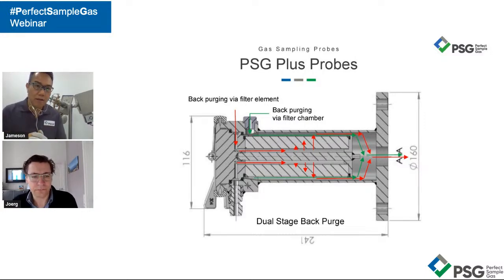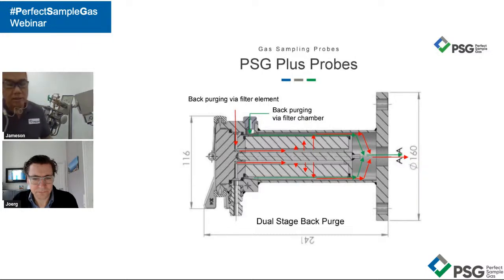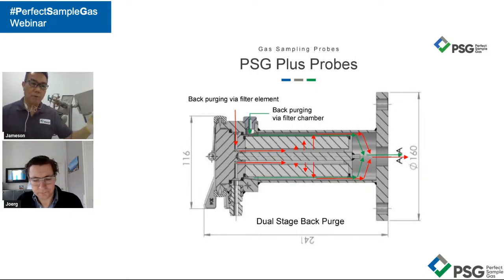They pulse in, they pop, and sometimes the particles still remain in the chamber. After pulsing a lot of times, we want the particles in the chamber to be delivered back into the process. So the second stage back purge brings all these particles back into the sample pipe and into the process. This is very important because in the CEMS system, we always talk about response time. The EPA, or TUV, always states that the response time from the calibration, from the probe to the analyzer, has a certain specification.